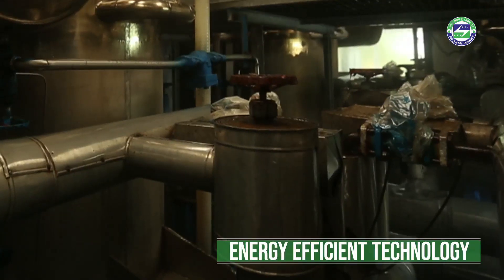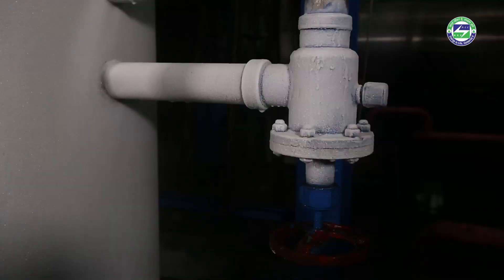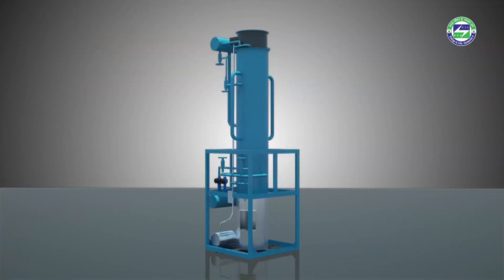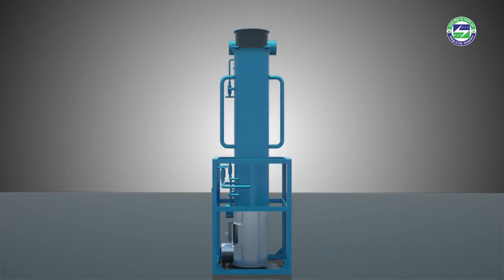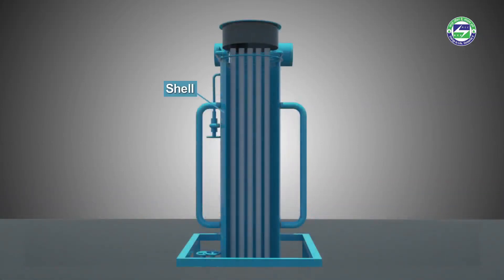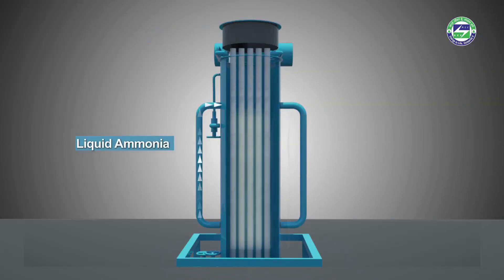An energy efficient alternative to conventional ice plants is the tube ice plant. The plant has an ice generator as its main part, which is a shell and tube vessel. The shell consists of water tubes with water distributors fitted on top of each tube, and the refrigerant ammonia fills the space between the tubes.